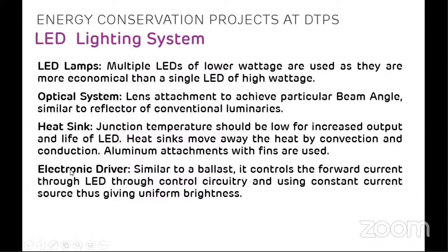And there is an electronic driver. A driver is similar to a choke or ballast. The only difference is in tube lights we use a copper ballast or a choke. Here we use an electronic ballast which consists of transistors. It controls the current flowing through the LED during starting condition, and maintains a constant current in running condition so that the brightness is uniform and not a flickering light.